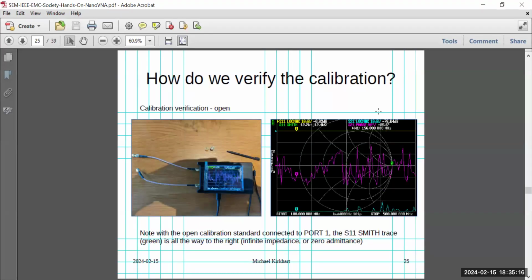Now, how do we verify the calibration? Over here you'll see it shows everything's applied, using the calibration we saved in slot 2. I'm trying to remember all these — it's not open, short, load, through, but more like directivity, reflection, and I can't remember what the S is, but the T is through, and the X is isolation. They're all showing there, so that indicates it's working.